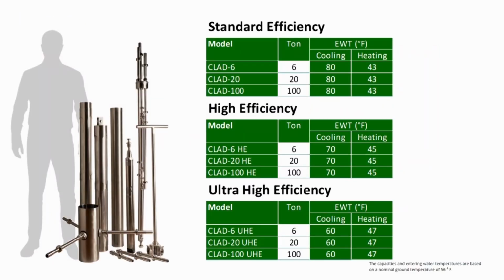We currently have 3 sized product offerings, and this is sometimes hard to fathom: a 6-ton, a 20-ton, and a 100-ton unit. Yes, we have a 100-ton unit. We need about 120 GPM from one well to produce 100 tons of heating and cooling from a single borehole, or a single water well in this case.